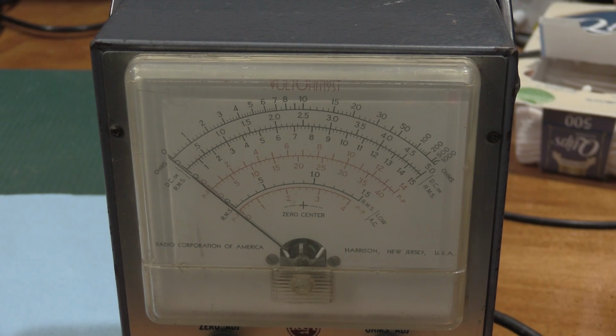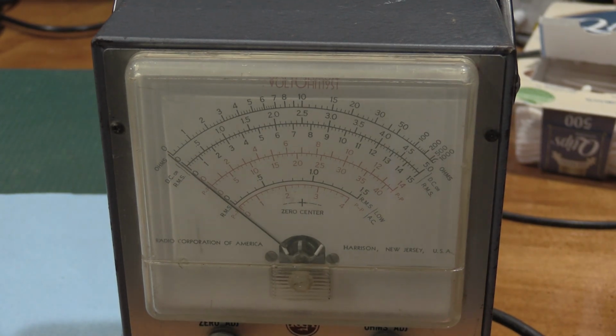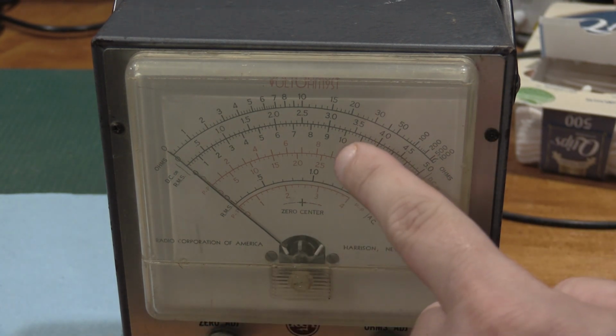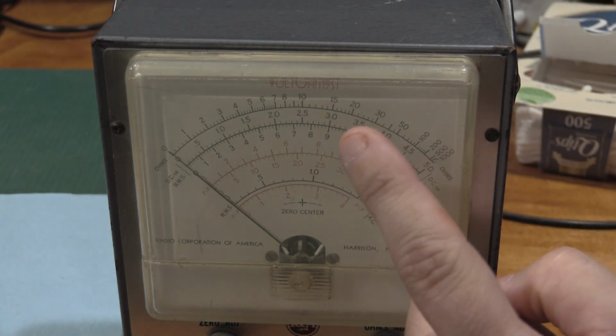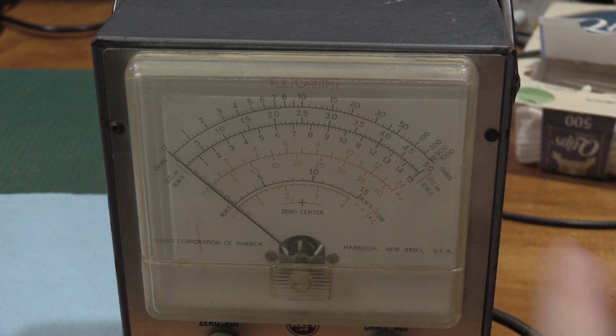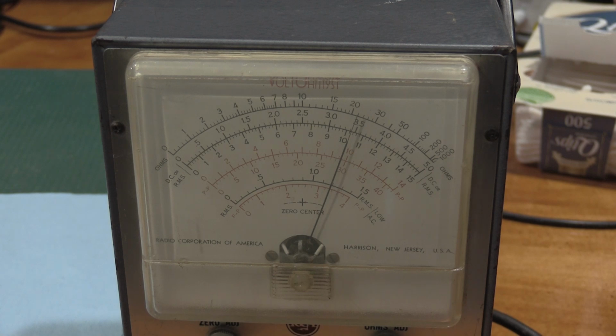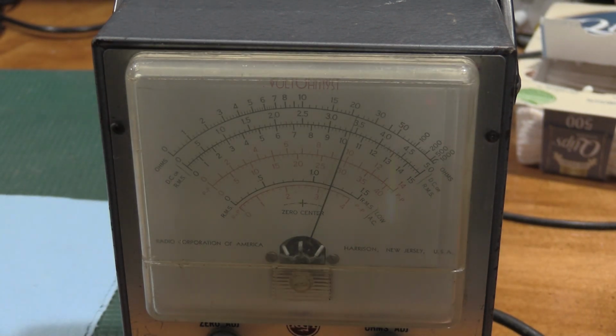but since the AC calibration is 100% pegged, we are going to put 100 volts at 60 hertz into the front end. What I'm actually looking for is above 100. So right here at the 10 on the B scale, I want to see above that. If I get above that, we're good to go, and I just need to let the gear warm up. If I get below that, we have other problems. All right, that will do. We will be able to align and calibrate this. Fantastic. Okay, so I just got to let the gear warm up, and then we can dial that in, and then we should be good to go.